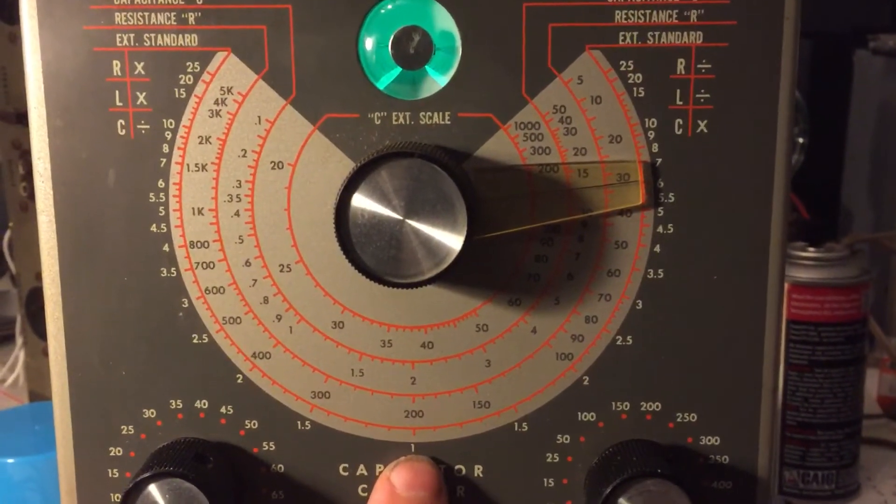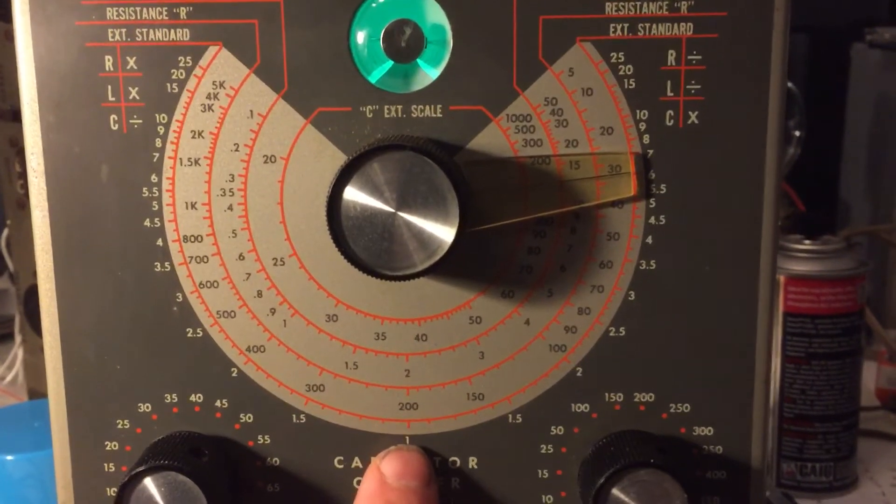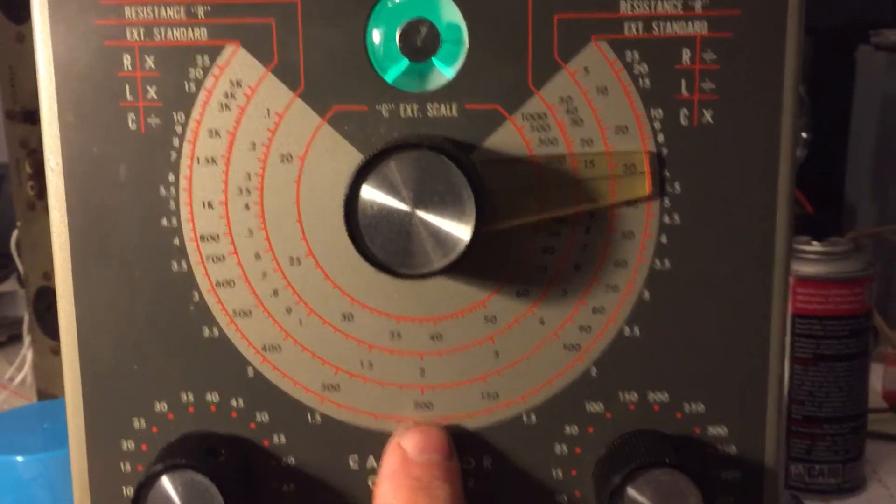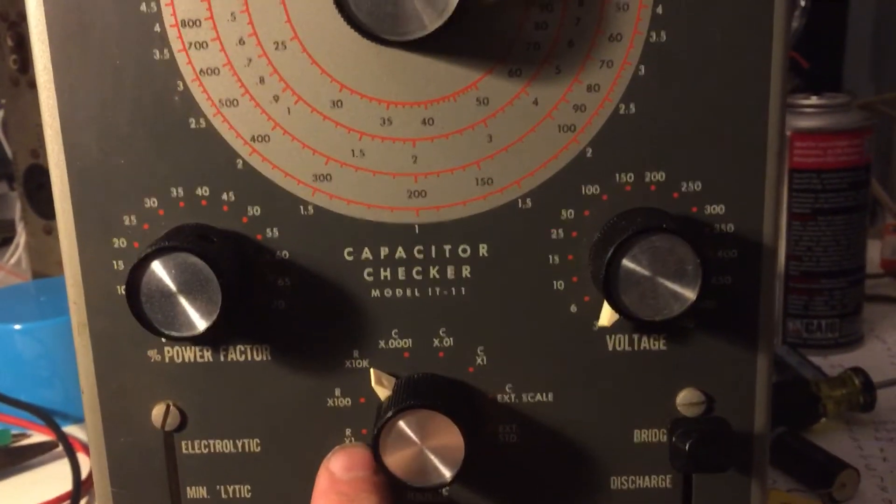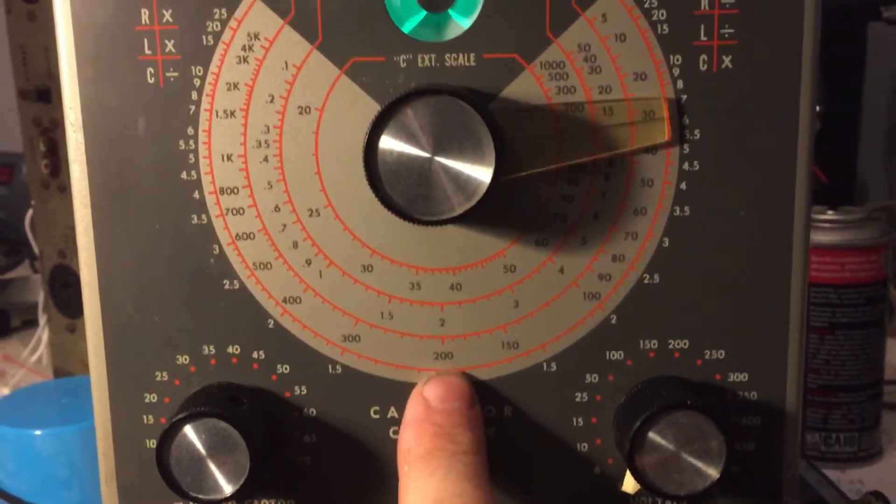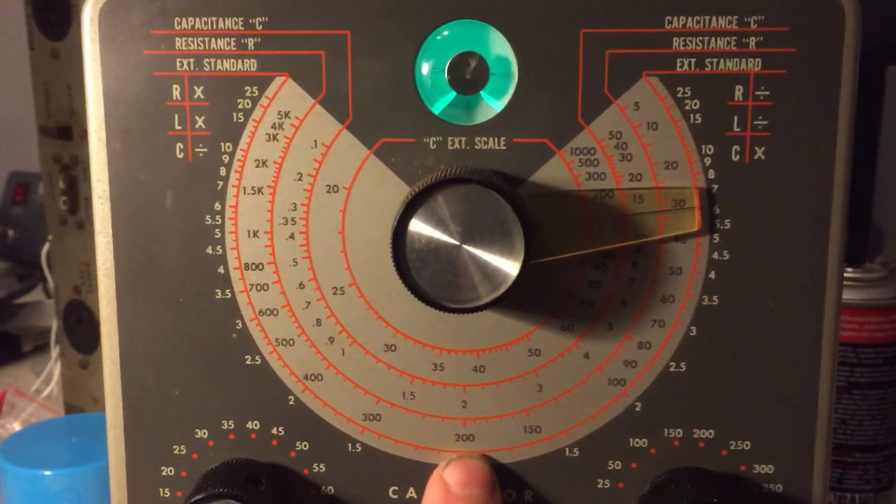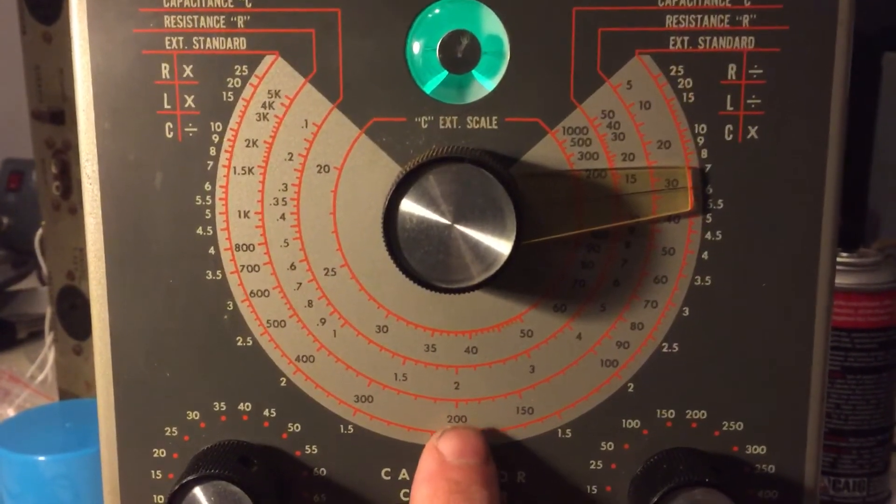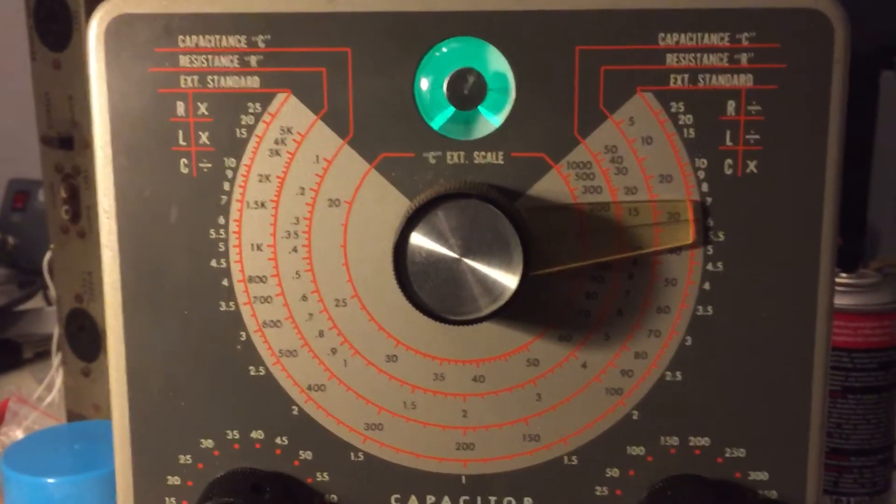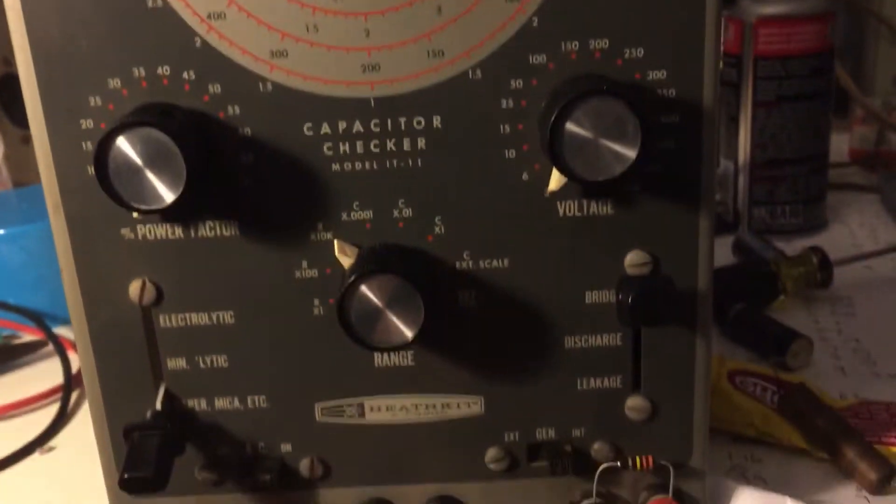Incidentally, the one which sits on the bottom and 200 over here is how you calibrate this unit by setting this to the X1 with a 1%, within 1%, 200 ohm resistor. When you bring it right down to the one it should balance out the whole circuit. That's basically how that works and this is how you check resistance on this unit.